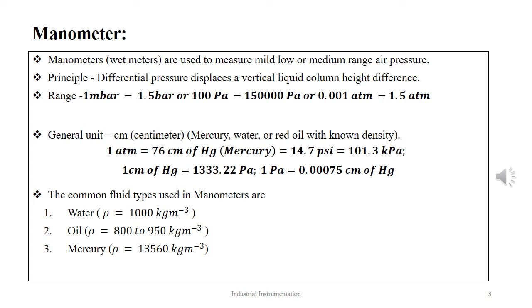1 atmospheric pressure is equal to 76 cm of mercury, or 14.7 psi, or 101.3 kPa. 1 cm of mercury is equal to 1333.22 Pa, and 1 Pa is equal to 0.00075 cm of mercury. The liquids commonly used in manometers are water of density 1,000 kg/m³, oil (specifically red oil) of density varying between 800 to 950 kg/m³, and mercury of density 13,560 kg/m³.